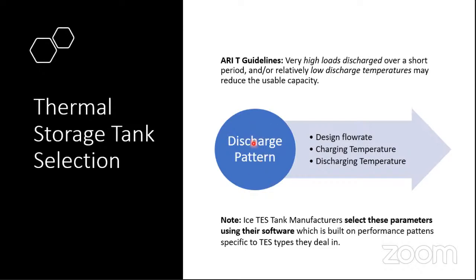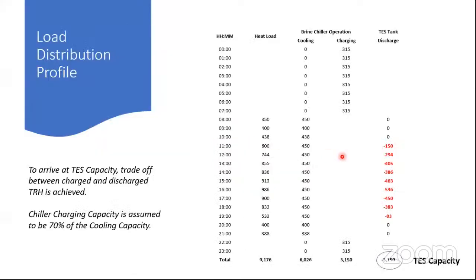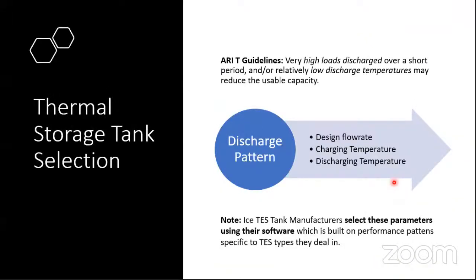Looking at the discharge pattern, my discharge pattern here is pretty healthy. It's a long duration of discharge. Had it been only 2 hours of discharge, let's say only 1 hour of discharge, then I might have had a lot of unused ice. So there is a term introduced here called usable capacity. What is going to be the usable capacity in a given scenario at a given inlet outlet temperature at a given flow rate.